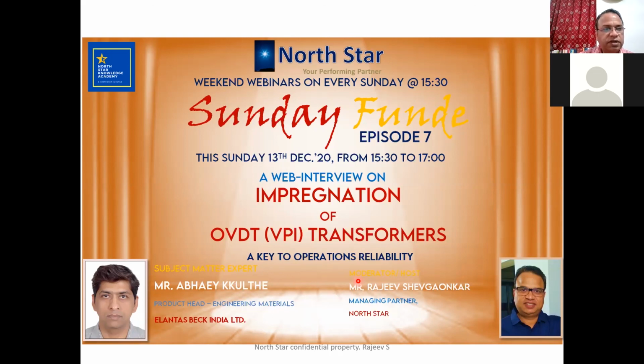One question is asked: whenever we dry out oil, how much temperature should be maintained during filtration? This is a very good question asked by Mr. Mahesh. Normally there is a misconception that if we increase the oil temperature during filtration, we get faster and better oil results, which is not true, because temperature alone is not responsible for removing the moisture from the transformer.